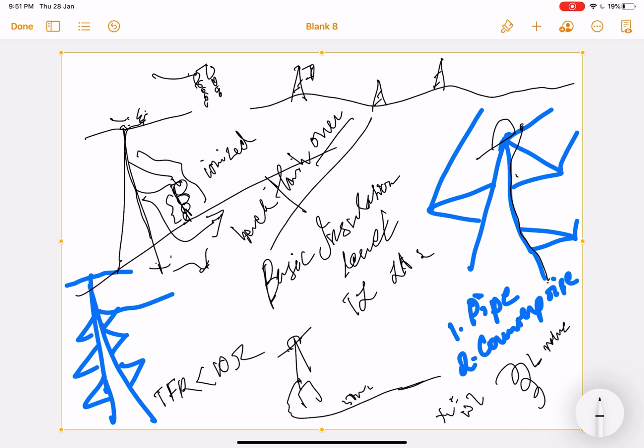Just like I explained in the back flashover case, in this case, instead of routing itself through the insulator and damaging it, the fault will be diverted. Since the LA is in parallel to the insulator, the fault will traverse through the lightning arrestor, and it will again travel into the conductor, but only till the next tower. Say in the next tower our earthing is good, so it will dissipate through that tower body to ground.